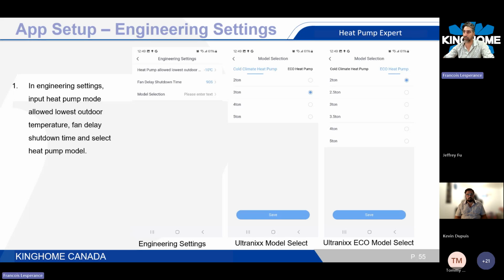And the most important one is the model selection. So you have to tell the system what you have installed. For example, if you have a cold climate heat pump, so the KU model, a 3-ton system, you just have to click here and the algorithm will select the COP from that unit, okay? If it's set as a 2-ton, you just click on the 2-ton. Same stuff if you have an Eco heat pump, say the KD model, now you just select the right tonnage you have installed. So basically the algorithm is different for each unit, okay, at that point.